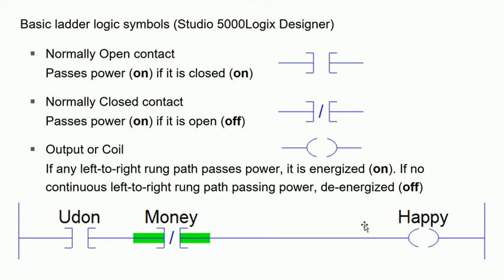One important thing to note is that contacts work exactly like switches in real life. If, for just a millisecond, Udon is OFF or not closed, then the output coil is going to be de-energized for that one millisecond. So in order to keep the output on for a relatively long and steady time, we normally do not use a contact directly like this, similar to a switch-and-LED-bulb circuit where the switch must remain closed steadily.